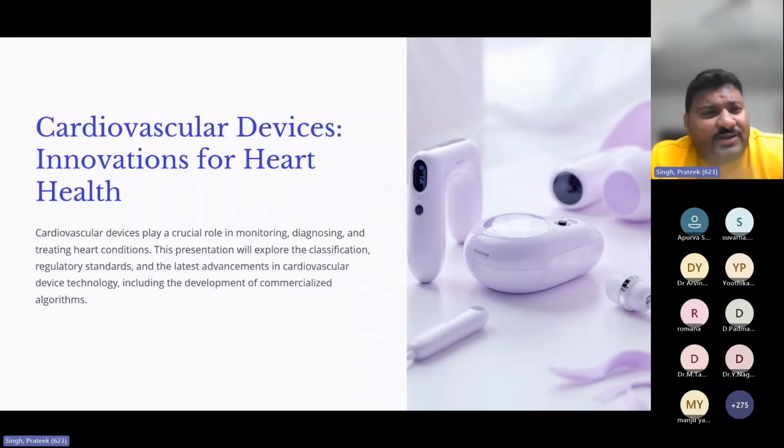You can run, you can do jogging, you can do multiple such things. So what's happening with that, because of the movement of these leads and device and the skin-to-electrode contact, sometimes the electrode comes out during this process. That will cause some noise in the ECG signals.